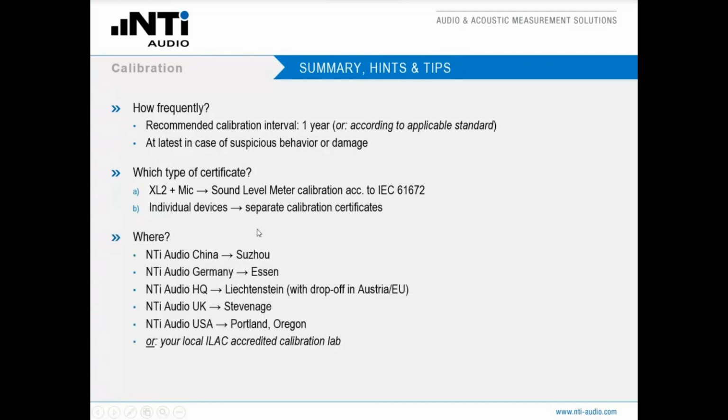Where can you do that? Here we have listed all the subsidiaries, the headquarters here in Liechtenstein, and all our subsidiaries worldwide who can execute these calibrations. Please feel free to send it to any of these places for your purpose. Otherwise, you can, of course, also send your device to an ILAC accredited calibration lab. Just keep in mind that they can only do the calibration, no adjustment, but in some cases it's even mandatory that you send it to such a calibration lab, as I mentioned before, for the type approved instruments.